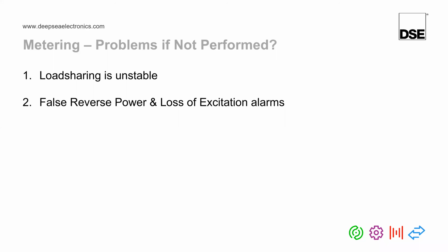Yeah, I'd just like to add further to that as well, actually, because it is a very good question. So a lot of the steps that we're going through now are applicable to an ATS. Yes, the governor and AVR we've just gone through, they technically aren't applicable to one of our ATS units. But if we're talking about synchronizing and load sharing application with the mains, if the DeepSea generator controller has bad control over the governor and AVR, that is going to affect your mains parallel, because at the end of the day, for the generators to synchronize with the mains, it has to have good control over the governor and AVR.